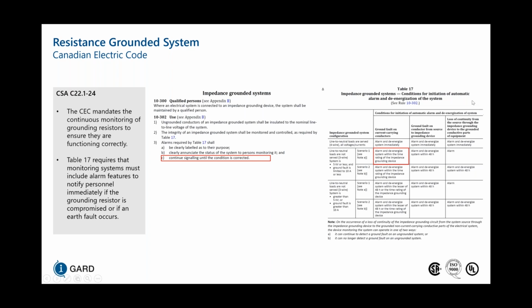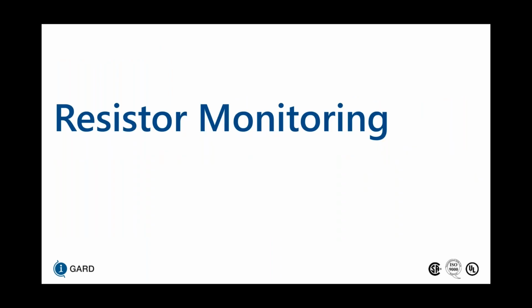And in that case, your system becomes ungrounded, and it's likely that this is the more dangerous of the two, arguably, because in an ungrounded scenario, your protection schemes downstream may not be suitable for an ungrounded system, since the methodology is different for detecting and locating issues.